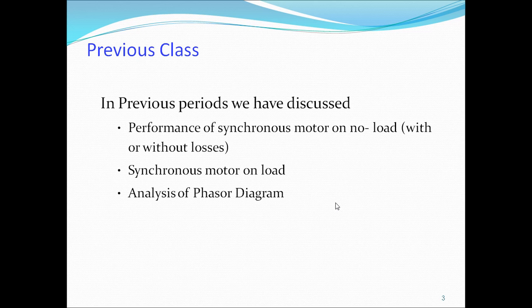The load angle alpha of the rotor adjusts itself such that the torque developed by the rotor is sufficient to carry the load and to supply the losses. If the load increases further, then a time comes when no value of alpha can satisfy. Then the motor pulls out of synchronism and it stops. The torque available at this moment is called pull-out torque.